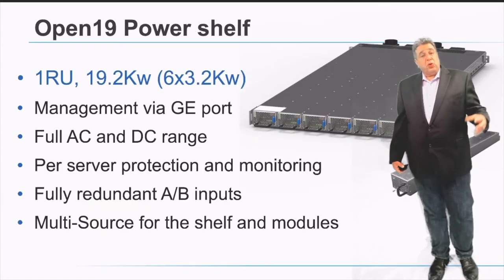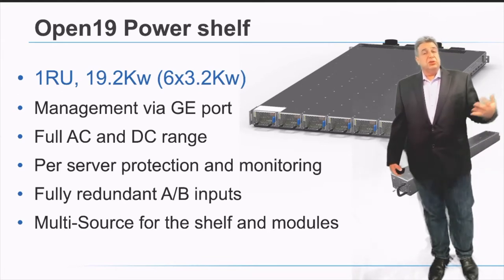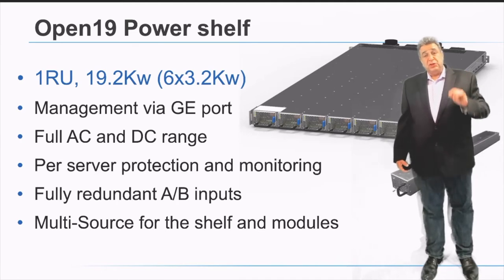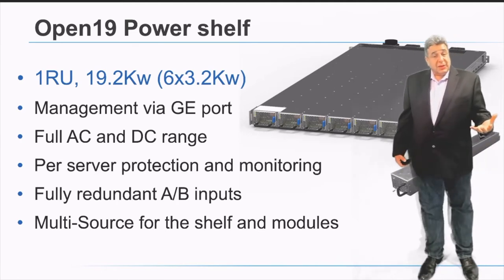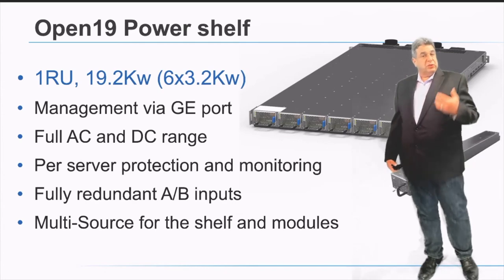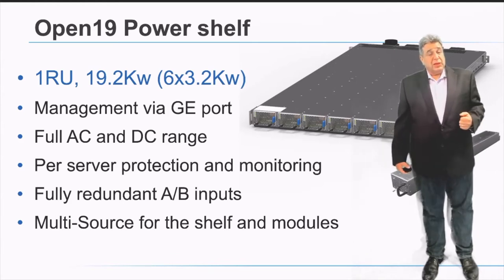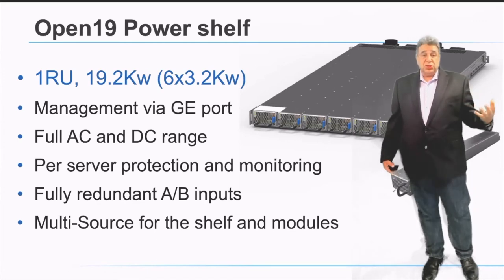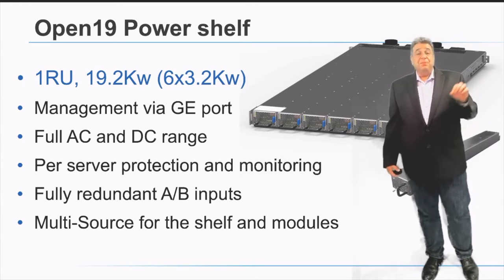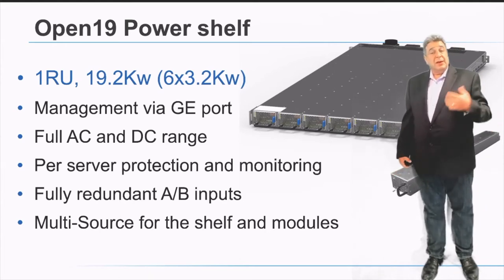We have a power shelf which is the core source of power for the whole rack. Every two cages operate with a single power shelf. Those two cages get a direct connection from the power shelf to each and every server, enabling us to monitor and protect each server independently without creating a shared fate among servers in the rack. We have a control management system inside the power shelf which connects to the rest of the world via a Gigabit connection, enabling fully remote management and real-time independent server monitoring. Those power shelves have 6 power modules and are available now.